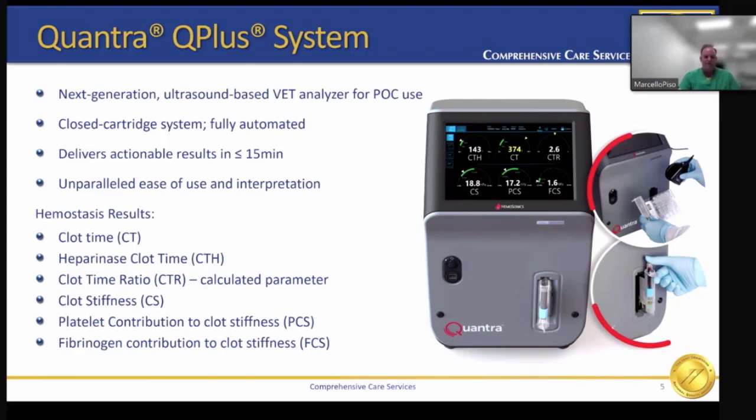The information derived from the Quantra is the clot time, the heparinase clot time — which allows us to see the clot time without the effect of heparin — the clot time ratio, or the calculation between the clot time and the clot time heparinase, and this tells us about the residual heparin on board. It also tells us the clot stiffness, or the strength of the clot, while providing us with both the contribution of platelets and the contribution of fibrinogen.